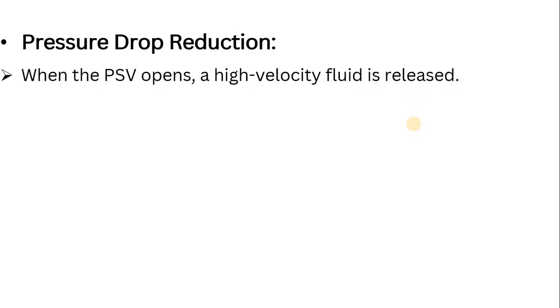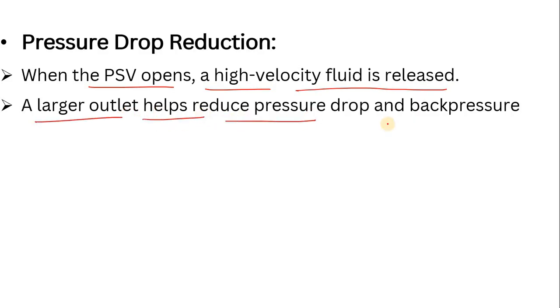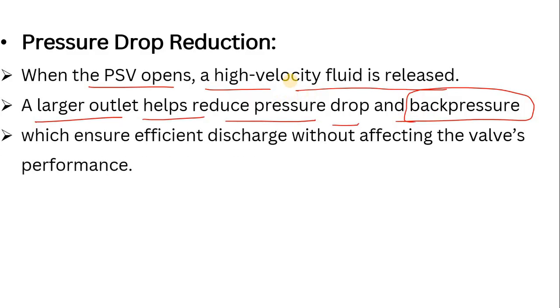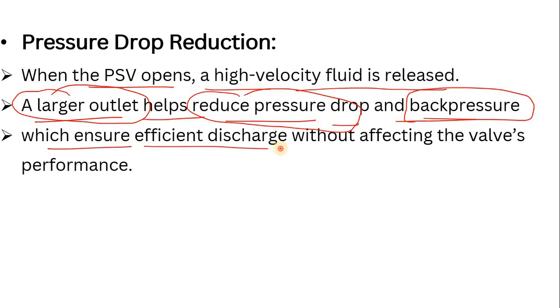One more point is pressure drop reduction. When the PSV opens or pops up, a high-velocity fluid is released. A larger outlet helps reduce pressure drop and back pressure. If the pressure drop delta-P is too high, the fluid will not go to the destination. If you select a larger outlet, it will definitely help reduce the pressure drop, ensuring efficient discharge without affecting the valve's performance.